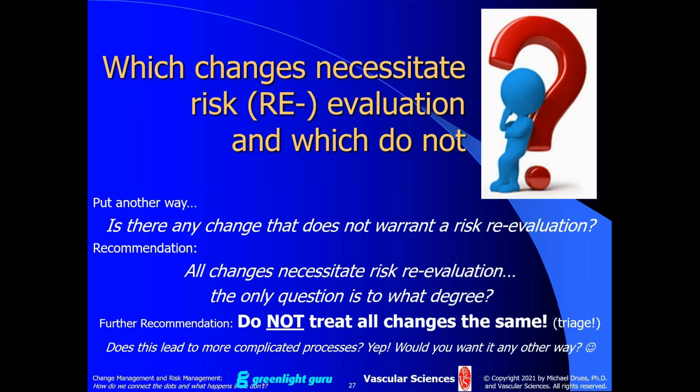Changes that have a greater impact on the potential safety and efficacy of a product, especially a Class 3 device like a PMA, should, it stands to reason, necessitate a much closer, much more detailed risk reevaluation than changing the color of the housing of the outside of some medical device, for example. I mean, to me, that's common sense.